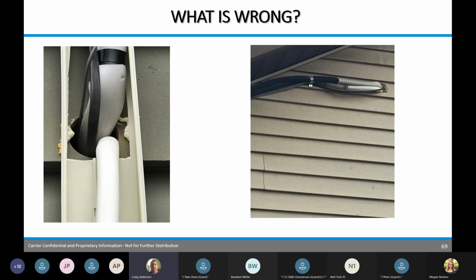This one here, they did put tracking on it. That's fantastic. They wanted to cover up their pipes. The thing they did not do is they did not seal the hole going from the outdoor to the indoor unit. So they're getting gushes of cold air or hot air. And where is that going? It's going right into the back of the unit on the sensors. It's affecting the sensors. It's making erratic operation, overheating, undercooling, anything like that. So check the holes where the pipes go through to the back of the unit as well.